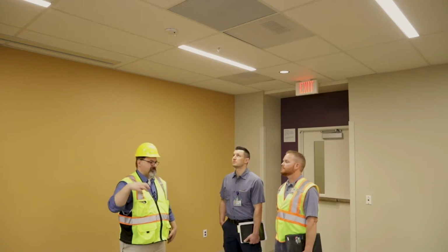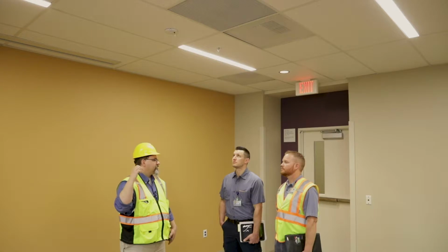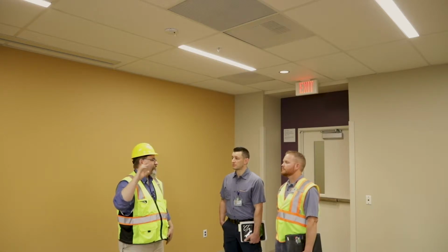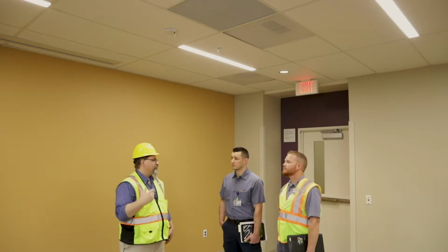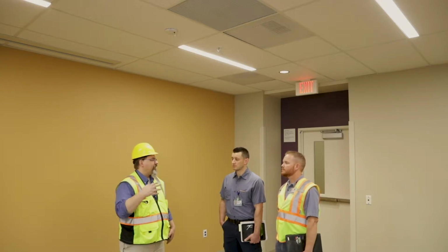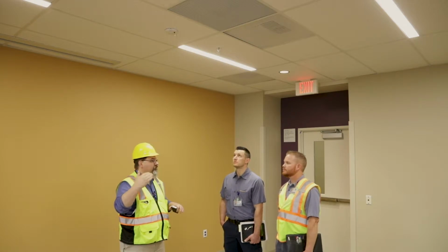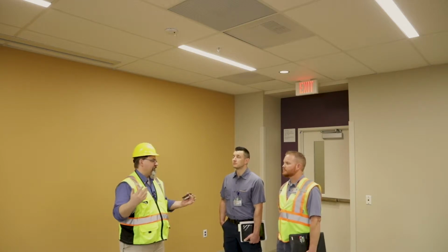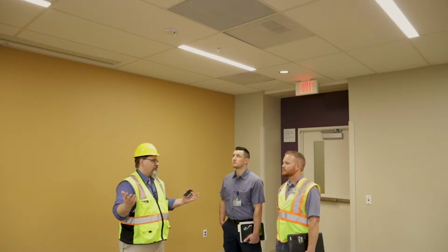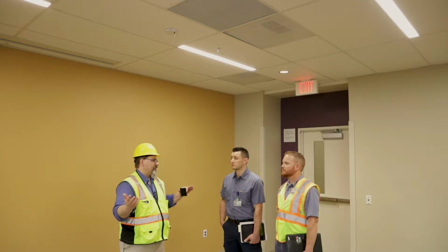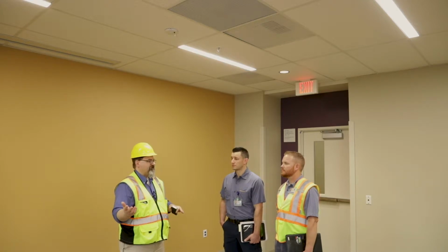Ultrasonic essentially rings the room. It receives a certain level of echo for the sound that it's putting out from those speakers. And when somebody moves in the room, even around a corner, that echo changes slightly and they're able to detect that. So both of those technologies are used to trigger it on, and then either of the technologies keeps it on for that window of 20 minutes. You re-trigger it, the counter resets to 20 minutes and then counts down to the next occupancy event. You see what I'm saying?